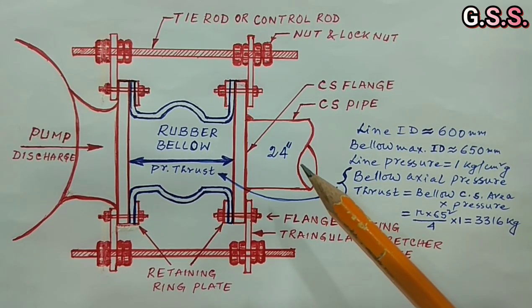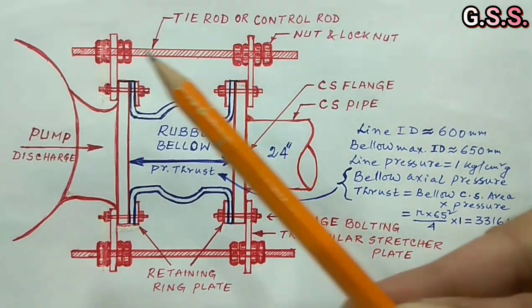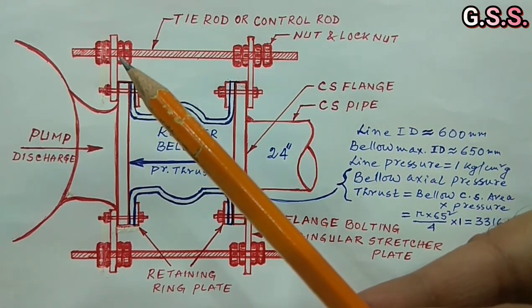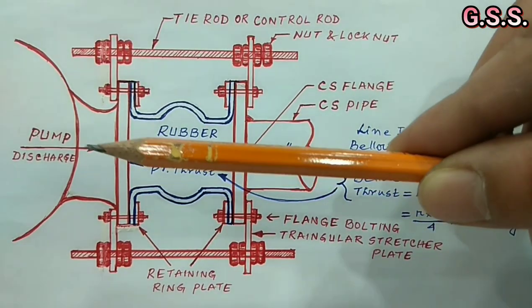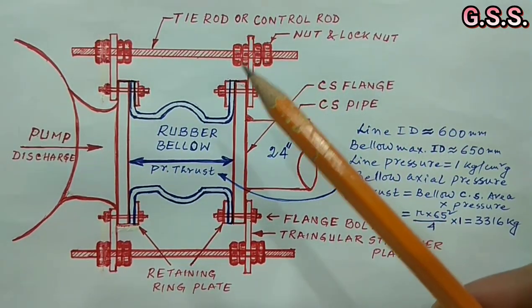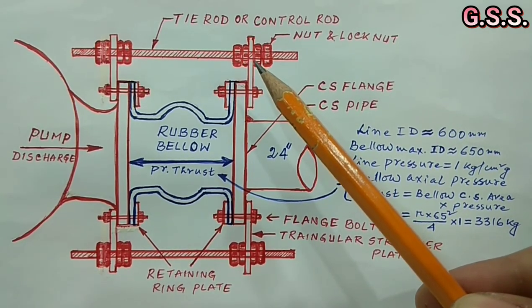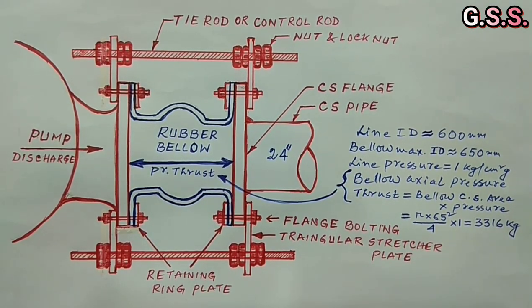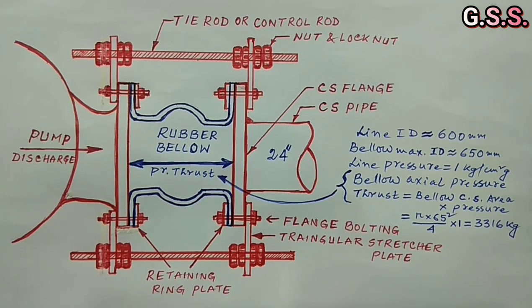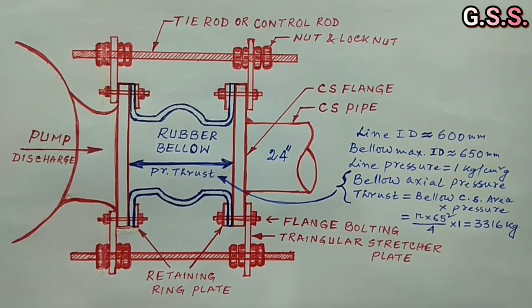So we have to keep tie rod nuts tight on both sides of the bellow and bellow will provide flexibility in lateral direction. We can provide only 1 mm gap here and 1 mm gap here so that bellow can be compressed or expanded by 1 mm only. Thereafter tie rod will take care of the load and nothing will happen due to this 1 mm movement.